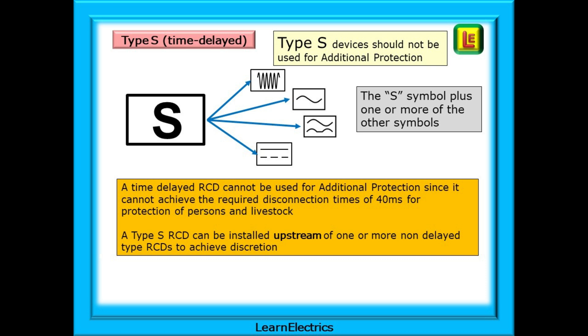The S type device is time-delayed, designed to respond a little slower. A time-delayed RCD cannot be used for additional protection since it cannot achieve the required disconnection time of 40 milliseconds for protection of persons and livestock. A type S RCD can be installed upstream of one or more non-delayed RCDs to achieve selectivity. Installing a bigger RCD upstream of two smaller ones does not guarantee the device nearest the fault will trip first — the only way to be sure is to install an S type upstream.